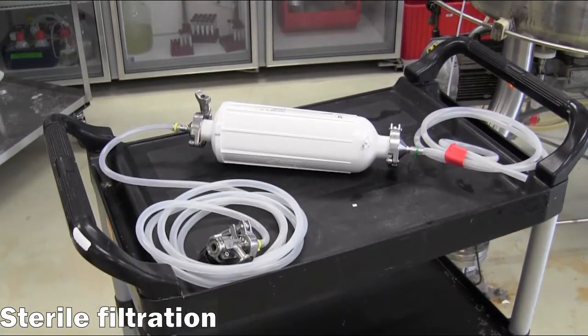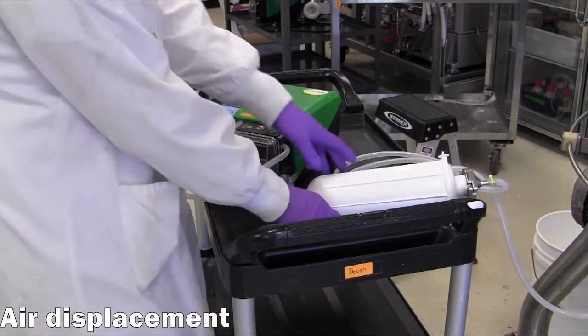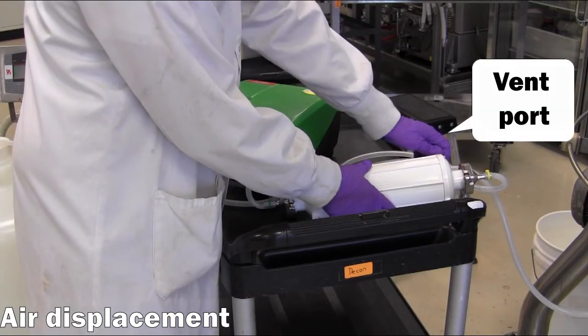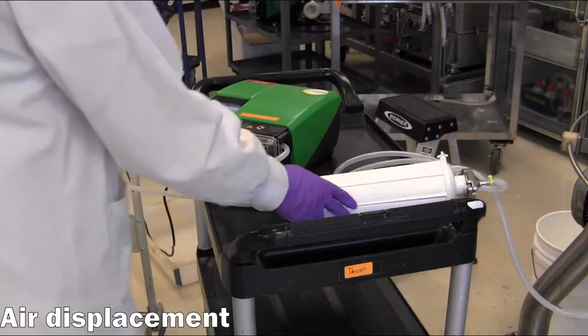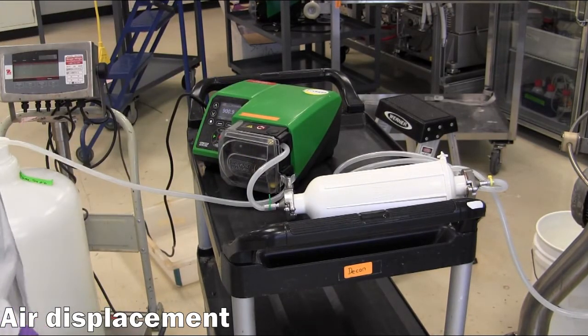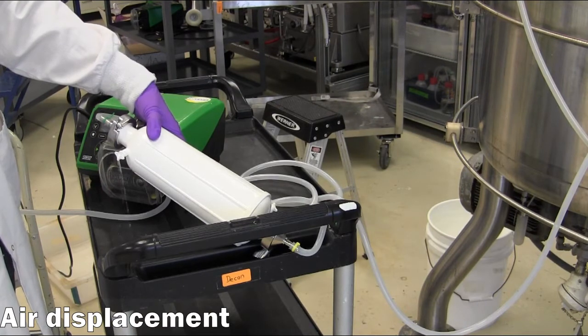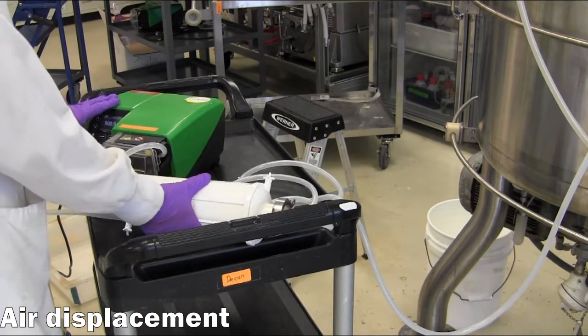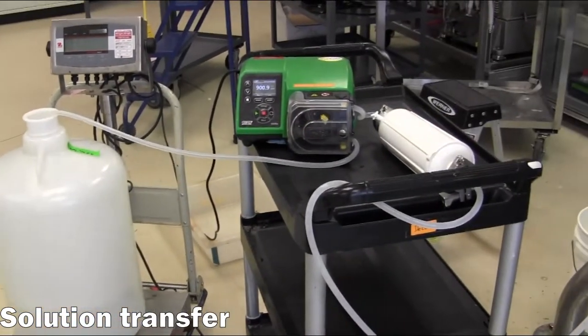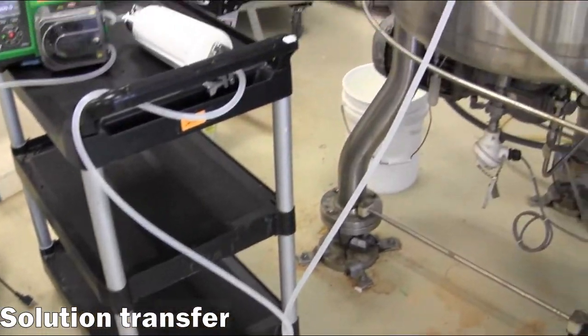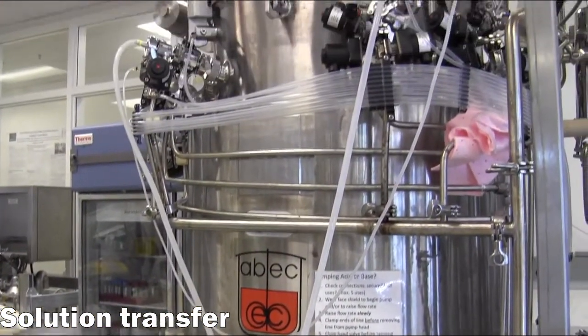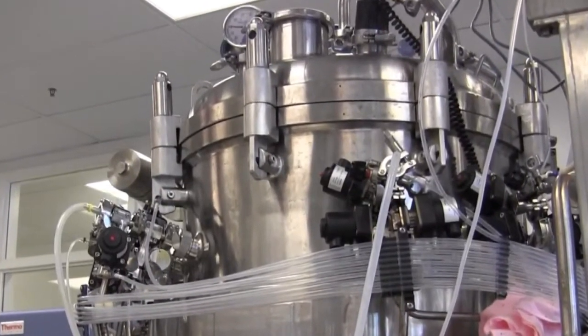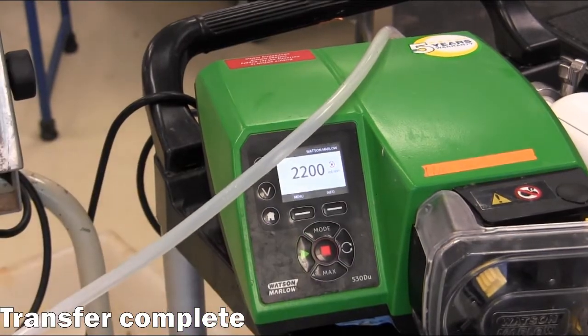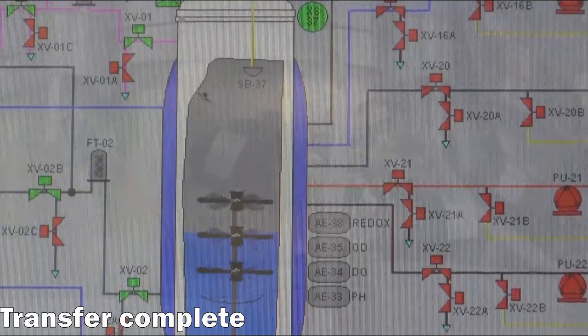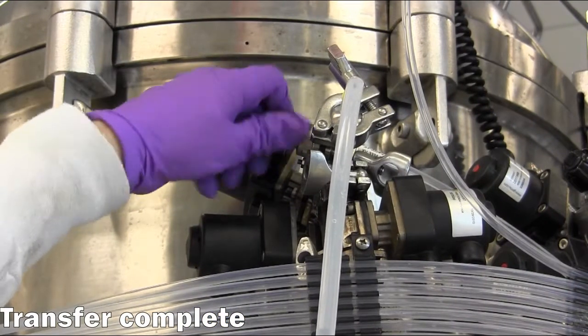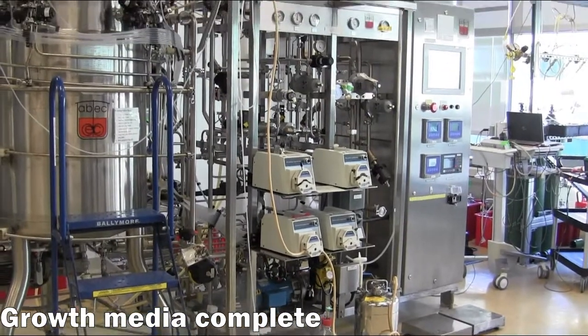Heat-sensitive solutions are passed through a 0.2 micron cartridge filter for sterilization instead of autoclaving. To use the cartridge filter, displace the air and wet the filter by starting the pump with the vent open. Once water comes out of the vent port, close the vent and transfer the solution into the reactor. Turn off the pump, close the valves, and remove the assembly as needed once complete. The growth media is now complete.